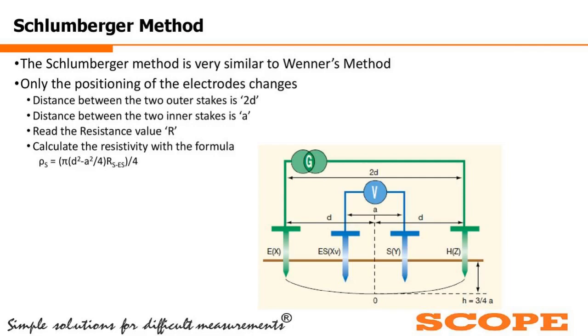The Schlumberger method now is very similar to Wenner's method, with a very small difference with respect to the Wenner's method. In Wenner's method, we have seen the 4 poles are used. Here in Schlumberger method also 4 poles are used. Now in Wenner's method, the distance between every pole is fixed. But here, the distance between these 4 probes is not fixed. We can change it. We have to consider the 0 position as the center position. From the center position, the distance to the 2 outer current probes we consider as D. And the distance between the 2 voltage probes we consider as A.